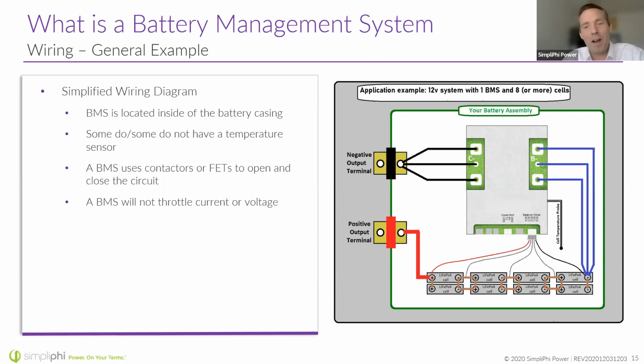This is just a simple wiring diagram showing the negative terminal of the battery, and the connection between the negative terminal and the BMS. Large amounts of current can flow through these, so typically when you buy a BMS, you're buying one with a limit on amperage, and it's also referred to as a 5S or 4S or 16S - meaning the number of cells that are in series in the system. So this 12-volt system is a 4S system, and it would have a limit based on amperage. Large amounts of current actually have to pass through the BMS itself, so you'll see fairly heavy connections if you look at a BMS.